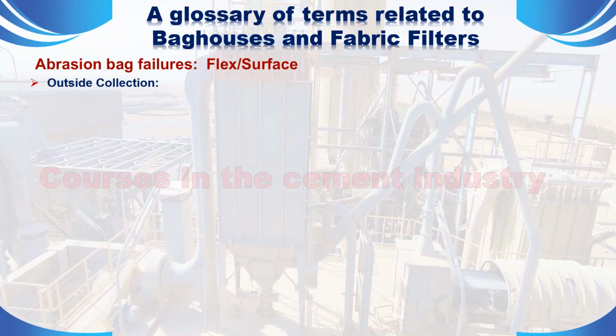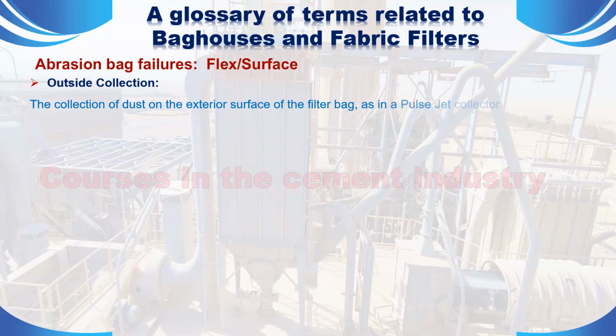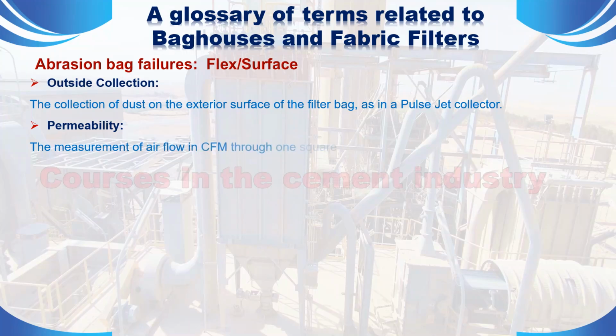Outside collection. The collection of dust on the exterior surface of the filter bag, as in a pulse jet collector. 29. Permeability. The measurement of airflow, in cubic feet per minute through 1 square foot of filter bag area at 0.5 inches H2O delta P.